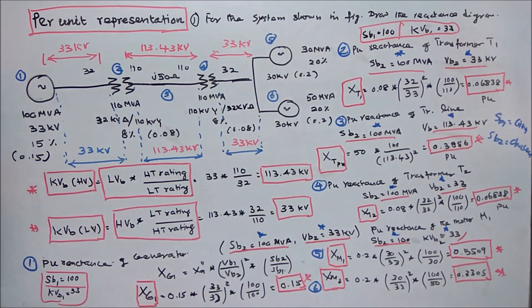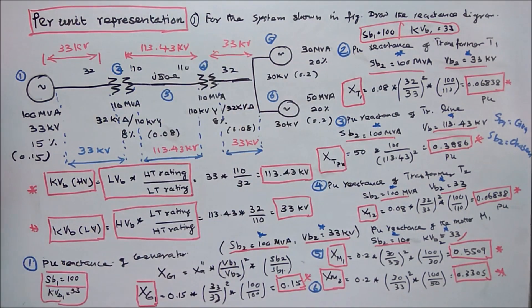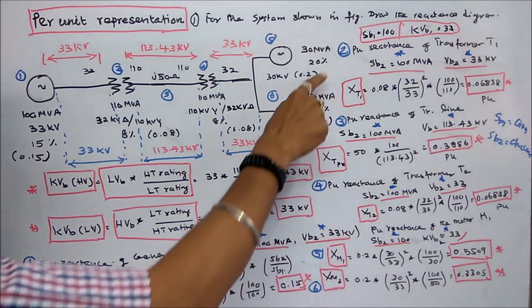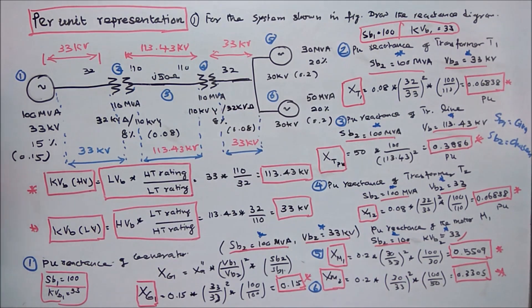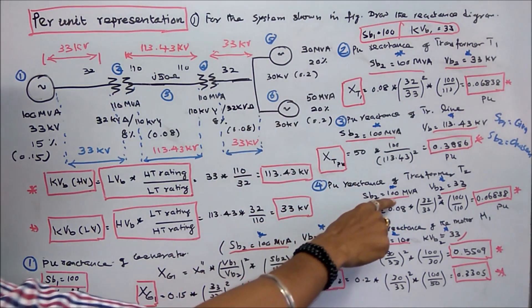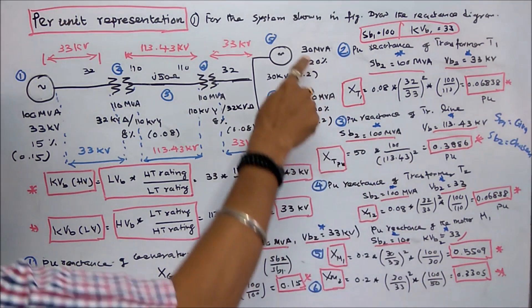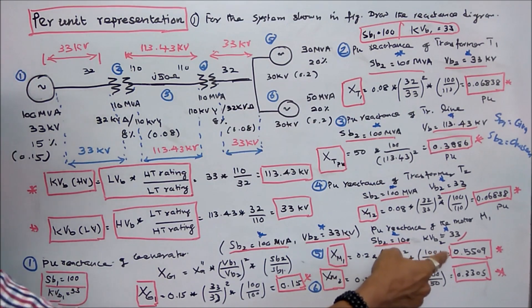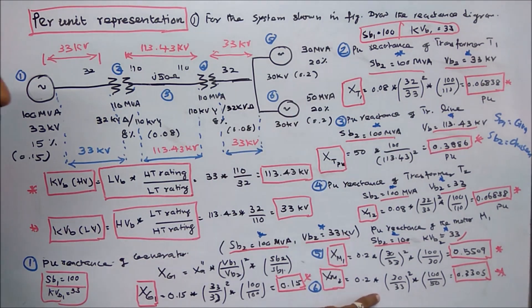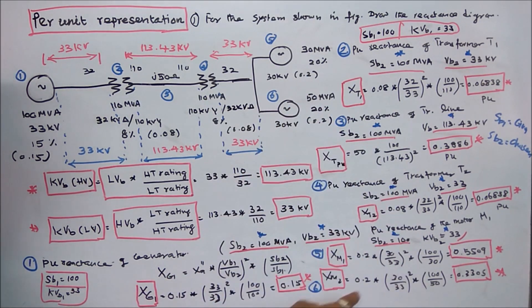The fifth is per unit reactance of motor 1, a 30 MVA motor. SB2 is 100, KVB2 is 33. Per unit reactance equals actual 0.2 into (VB1/VB2) squared, that is (30/33) squared, times SB2 100 divided by given 30. That equals 0.5509. Similarly for motor 2 (50 MVA given): 0.2 into (30/33) squared times 100/50, which equals 0.3305.